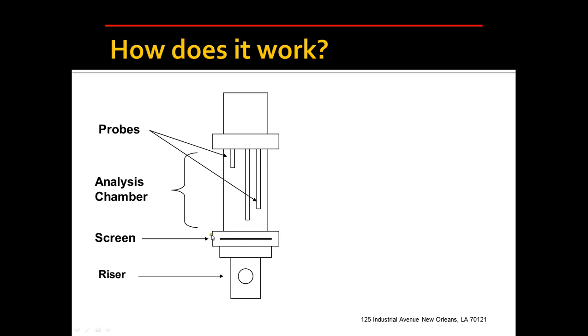The bottom of the system is a riser. This is roughly a 2.5 inch OD stainless steel, typically welded into your system. There is a pressure transmitter, which is mounted on the side of it. There's a ball valve typically, which is not illustrated here, which is between the riser and the screen. In the analysis chamber itself, you have two probes, a higher and a lower probe. This center probe-looking device is actually a screen sprayer and doesn't actually participate in the analysis process. The length of these probes and the internal diameter of this acrylic plastic tube are adjustable.